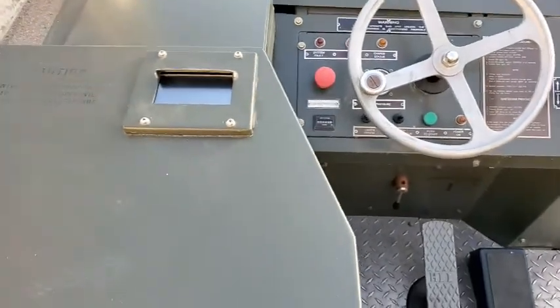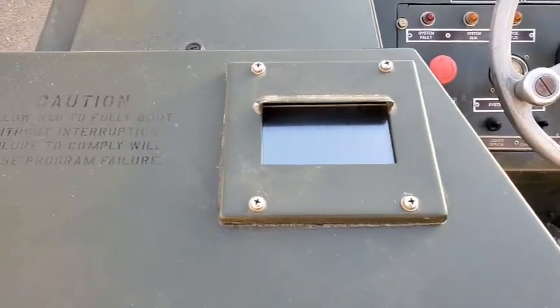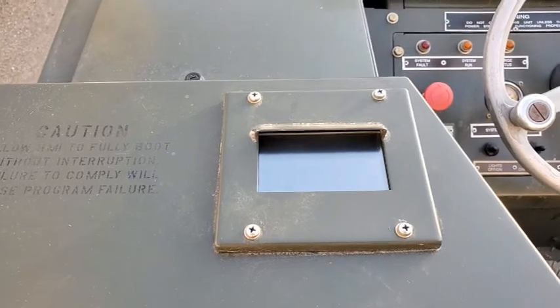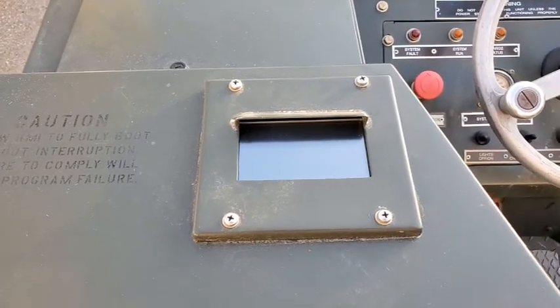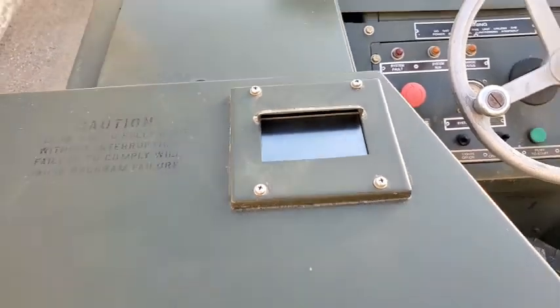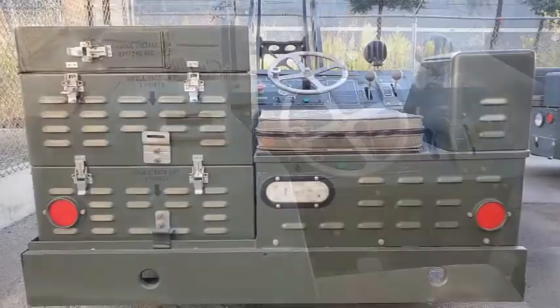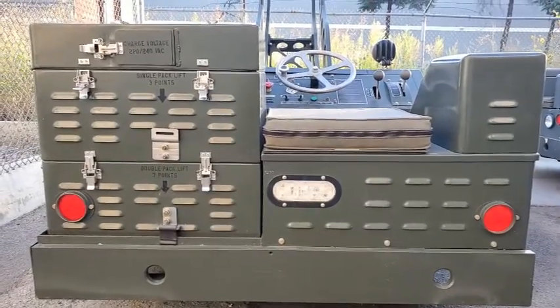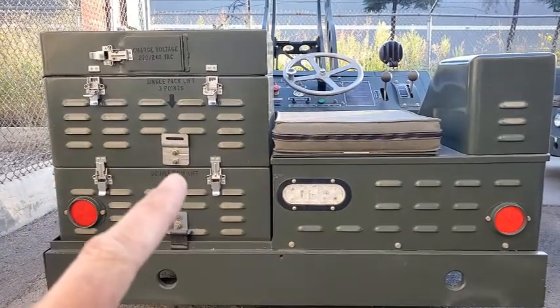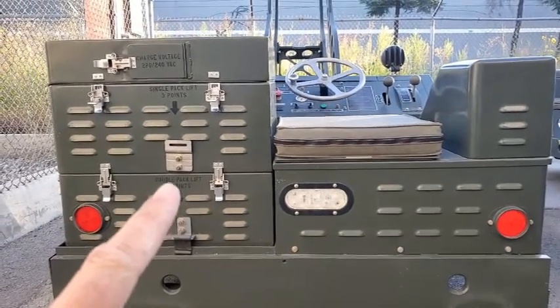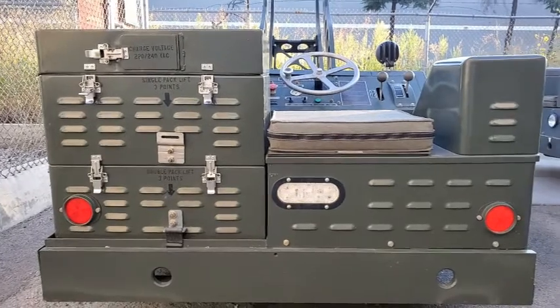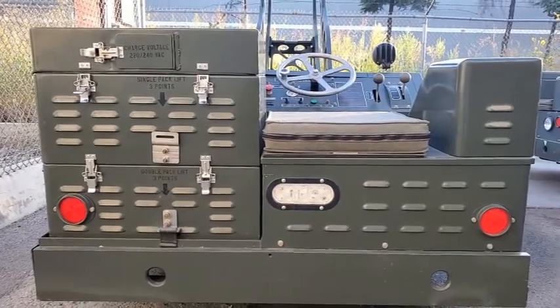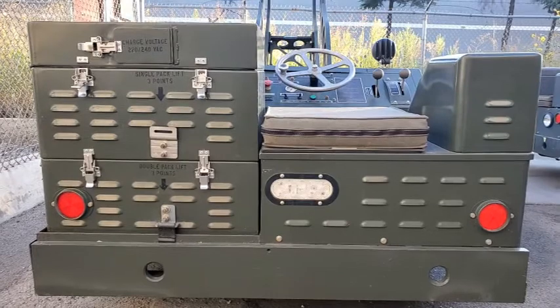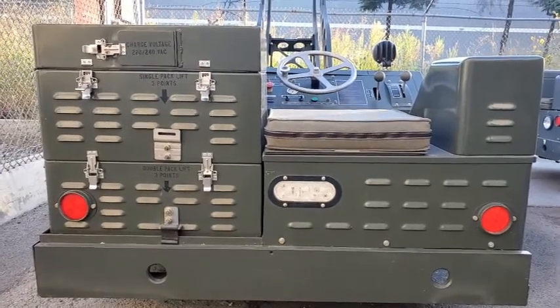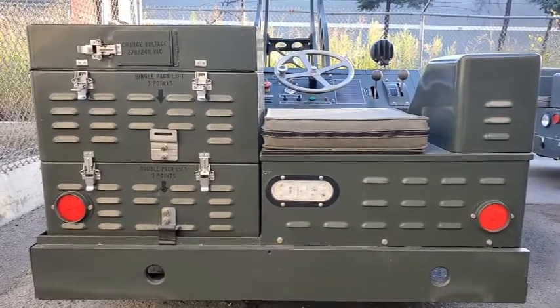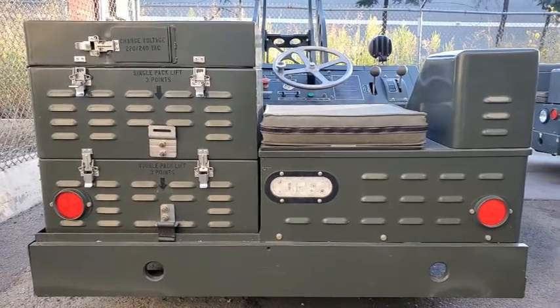Up here on the battery pack, we have the HMI, human machine interface. Once this is booted up, you'll be able to interact with this battery pack. You can see on the battery pack at this time it's got a lift lug installed on it. There's 3 lift lugs that come with a strap in a special kit to lift the battery pack off and to separate the battery pack halves. It typically does not come with the unit, it needs to be ordered separately.